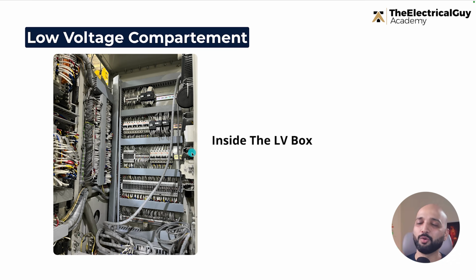So that's the low voltage box, and it has to be low voltage because generally the maintenance staff, the engineers will go and operate with that. They will not go and touch the circuit breaker compartment. They will not go and touch the cable compartment on a regular basis, right? Or when the supply is on. But the low voltage side is something you can go and touch on a regular basis to check the indication, to set the things. And you can also do it when the supply is on. So that's why the low voltage compartment is very, very important. I hope you understood what is the low voltage compartment, what are the different things that we have provided inside that.